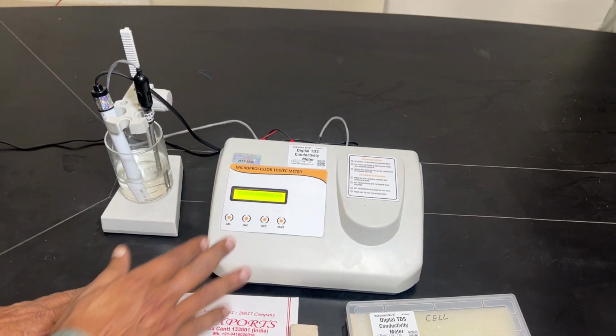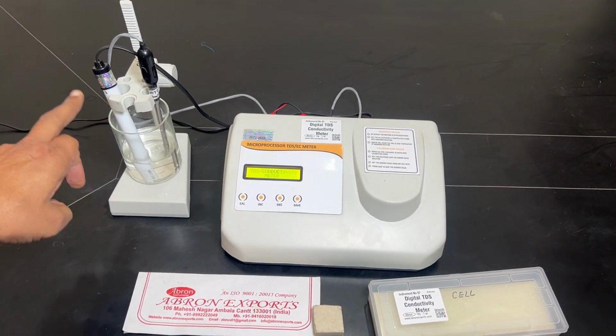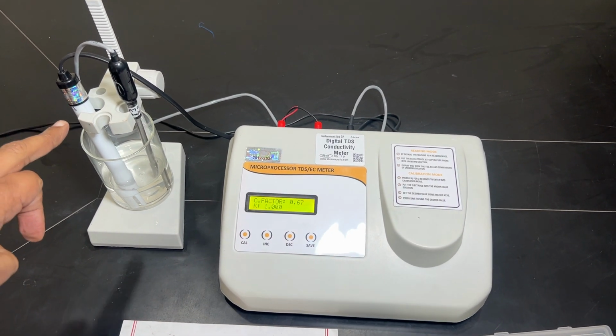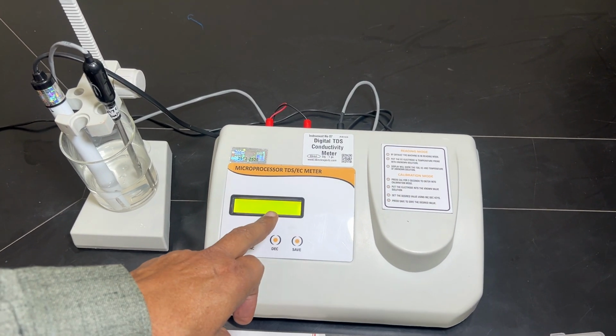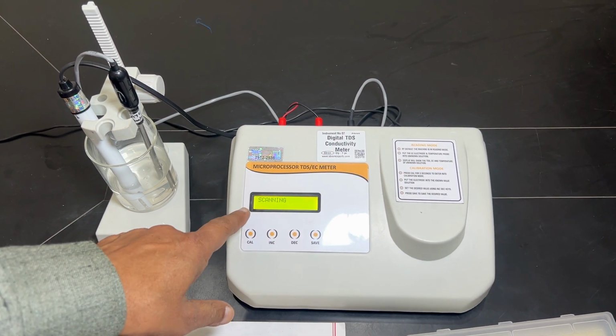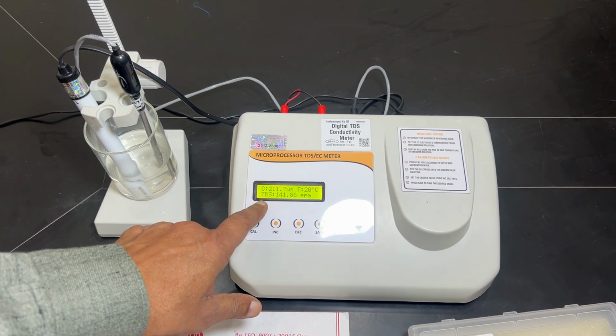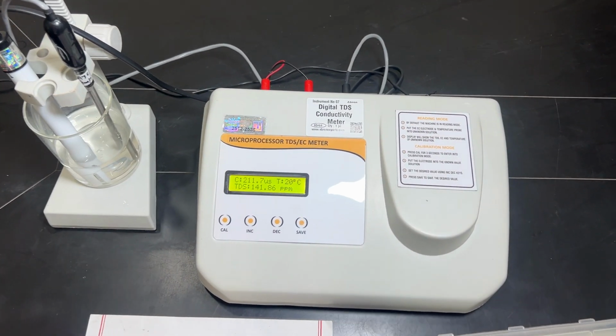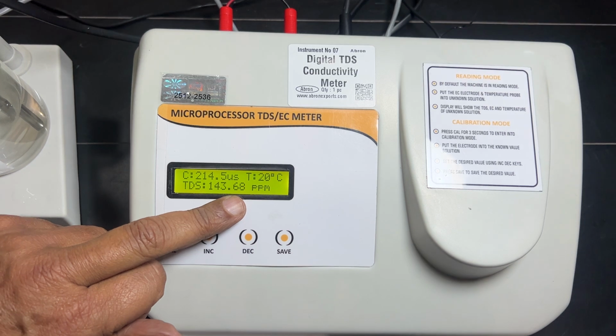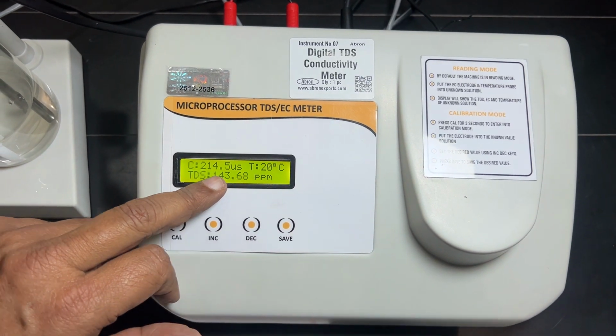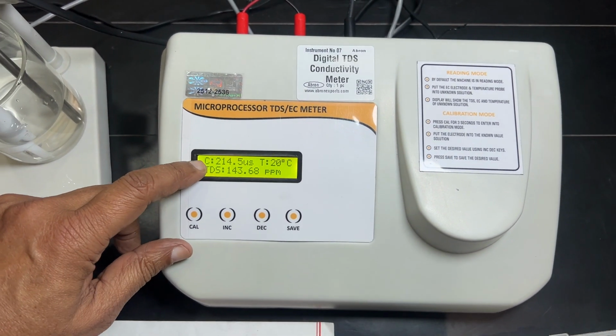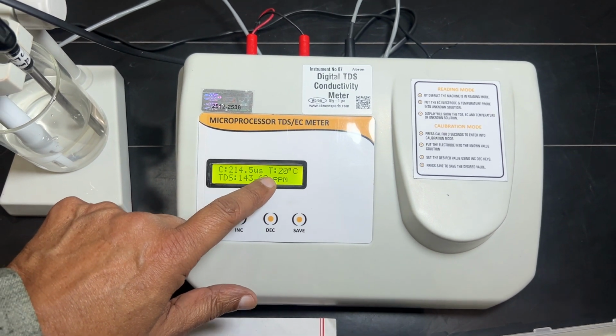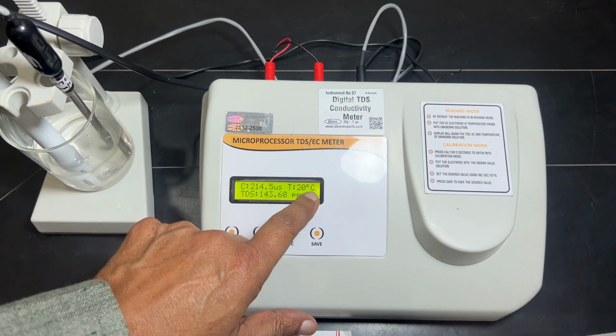When we switch it on, it automatically senses the sensor, the conductivity cell, and this factor is already there. Scanning is done. The reading will be showing you TDS. I show you the TDS is 143.68 ppm is the reading of this solution, and conductivity is 214.5 uS. Temperature showing is 20 degrees centigrade.